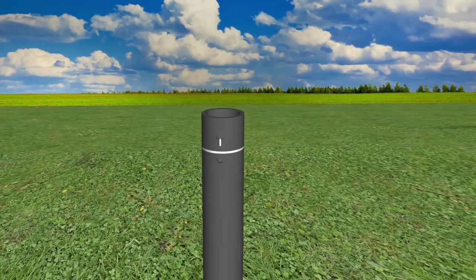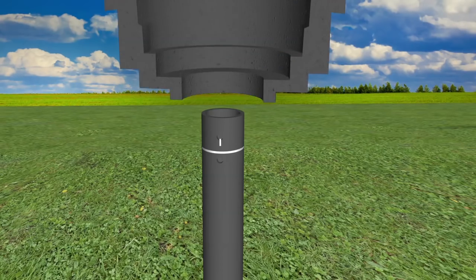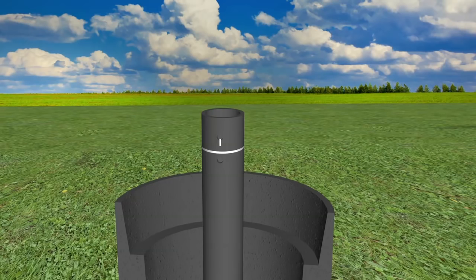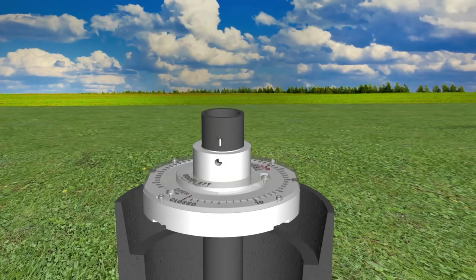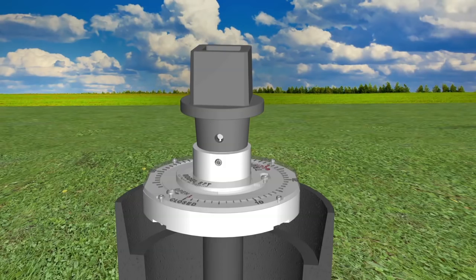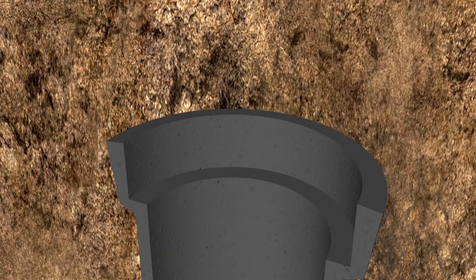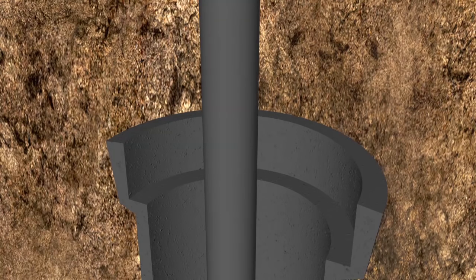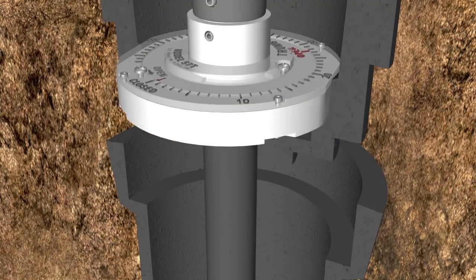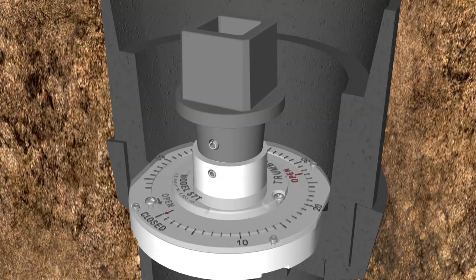Remove the 2 inch nut and position indicator from the stem. Slide the cast iron housing adapter onto the stem. Now slide the valve position indicator back onto the stem and install the removable pin into the drilled holes. Next, place the 2 inch operating nut back onto the stem and install the removable pin. Place the cut to length extension stem assembly back into the valve box, making sure that it is properly mounted on the operating nut of the valve.